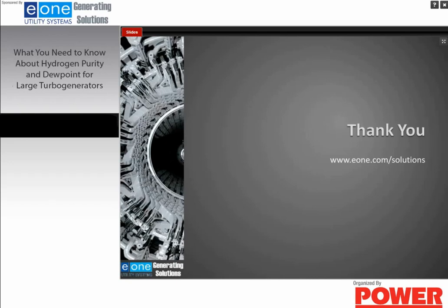Anytime you mention a fan in this presentation, you're referring to the rotor-mounted fans inside the generator case? That is correct, yes. Some OEMs will use fans. Some will use only one fan on the rotor. Some will use two fans. And some use a device that's called a blower and not a fan. So, yes, I am referring to the fan or blower that is located inside the generator case. Okay, and what frequency do you recommend for calibrating a thermal conductivity meter, a gas density meter as well? I can only answer for my piece of equipment, and we recommend every 6 months. I'm aware of analyzers that remained in calibration past a year, but our recommendation is still that the unit be calibrated every 6 months.